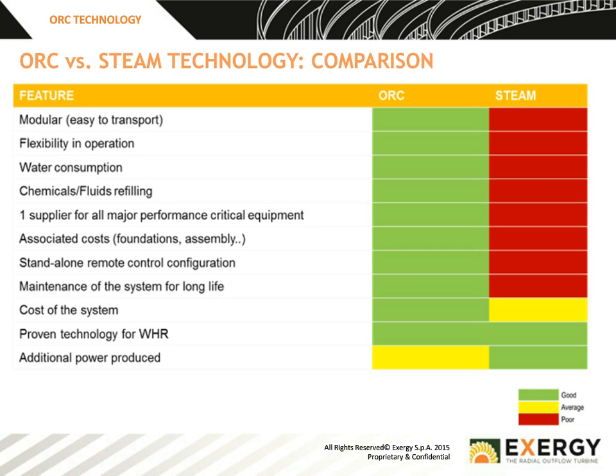Both of them are proven technologies, and then additional power produced. So here we're saying steam is potentially more efficient, but bear in mind that steam is generally used at higher temperatures. So at lower temperatures, steam may not even be an option, let alone more efficient. And then at the border point, you get the point where both of them are as efficient as each other, and at high temperatures, steam can be more efficient and usually is more efficient at the very high temperatures than ORC.